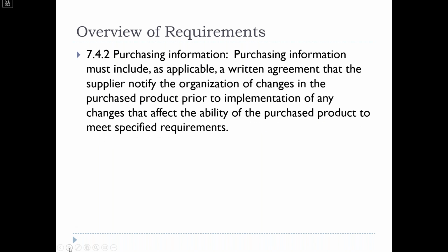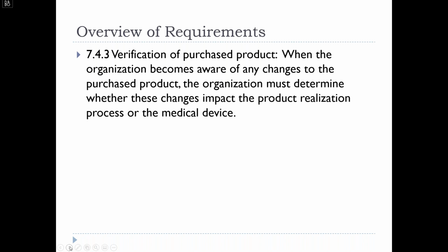Purchasing information needs to include, as applicable, a written agreement that the supplier notifies the organization of changes in the purchased product prior to implementation of those changes that affect the ability of the purchased product to meet requirements. That could be their customers' requirements or regulatory requirements. And when the organization becomes aware of any changes to the purchased product, they must determine whether these changes impact the product realization process or the medical device and react accordingly.